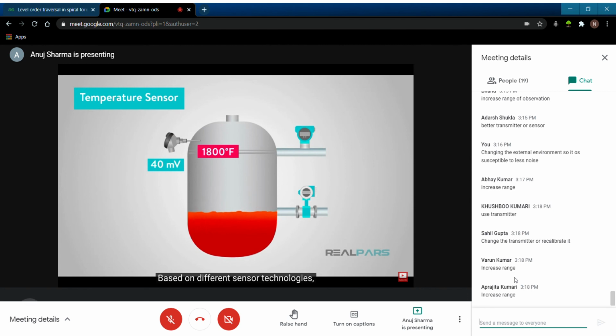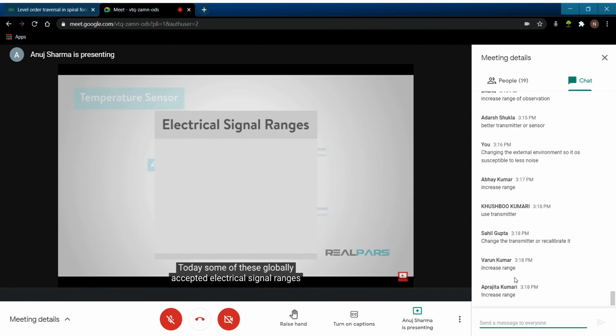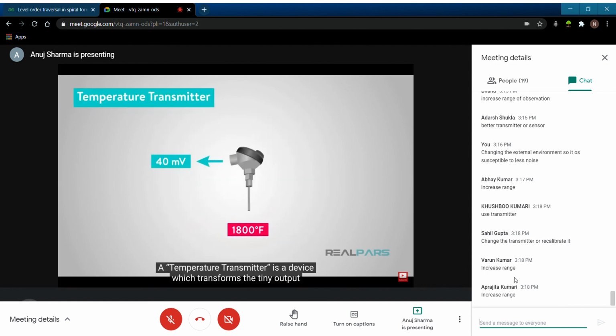Based on different sensor technologies, this signal may have different ranges, and for industrial applications, I need to have my signals limited to some universally accepted electrical signal ranges. Today, some of these globally accepted electrical signal ranges are 4 to 20 milliamps, 1 to 5 volts, 0 to 10 volts, etc. A temperature transmitter is a device which transforms the tiny output of a temperature transducer to one of these standard signal ranges.